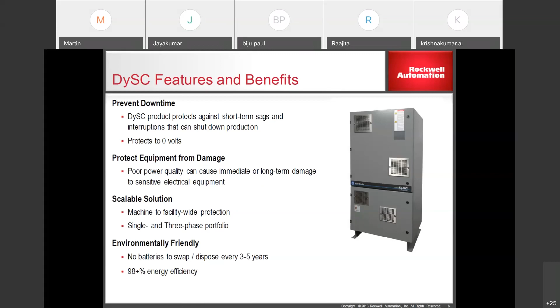So this is how the DySC is internally displayed. You can see that the green line shows how the utility power is fed to the load when there is nominal voltage, which is above 87%. The DySC operation will always start below 87% of the voltage. So when normal operation happens, the green line indicates the power flow. We have a static switch inside, and the static switch connects the utility and the load.